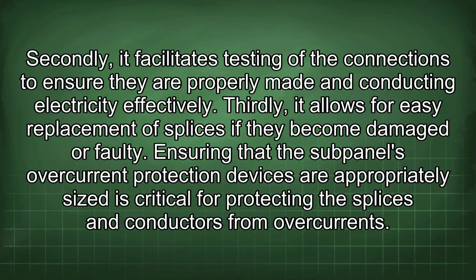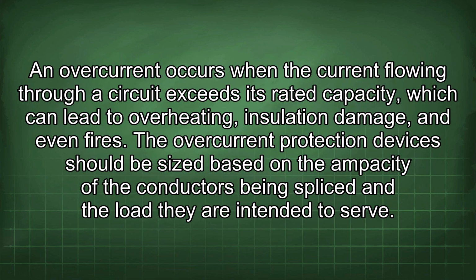Ensuring that the subpanel's overcurrent protection devices are appropriately sized is critical for protecting the splices and conductors from overcurrents. An overcurrent occurs when the current flowing through a circuit exceeds its rated capacity, which can lead to overheating, insulation damage, and even fires. The overcurrent protection devices should be sized based on the ampacity of the conductors being spliced and the load they are intended to serve.